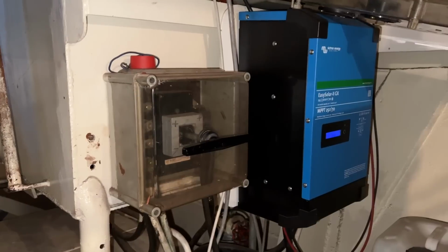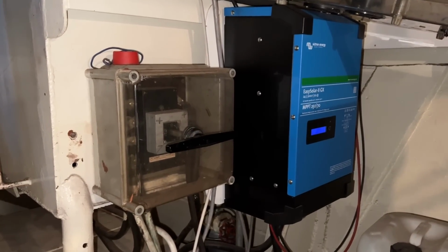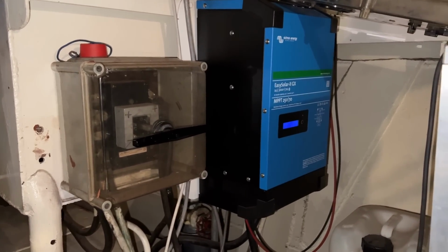The next important thing is getting some power supply to the console. Most equipment uses 24 volts direct current, because that's what's coming out of the batteries. There's a main switch for the 24 volts located in the engine room, but since most 24 volts consumers are fused underneath the console, I'm installing a secondary switch so I can isolate this switchboard and work on it safely.